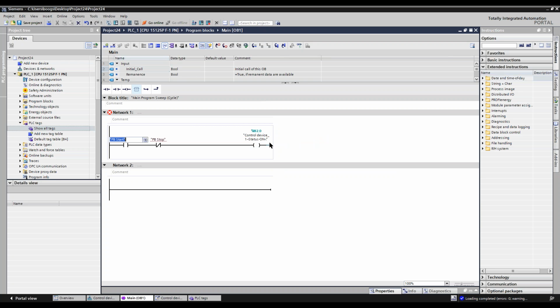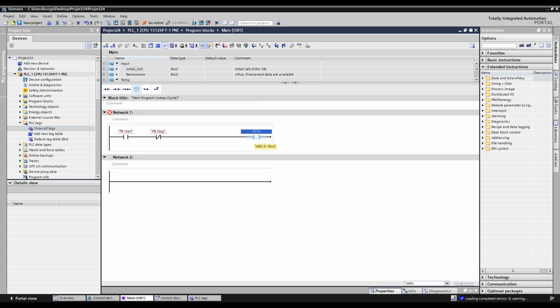Now I don't remember what the tag name is, so I just leave it blank and the tags automatically pull up. So I could scroll down here and look for motor on or interlock, and here's off or here's on. I could drag that over and I want this one to go clockwise, and that's what I hit for that one. And there we have device. Well, that's status, so that's an input. I apologize, I grabbed the wrong thing. So let's go back here. I don't want the status, I want the actual bit that turns it on.